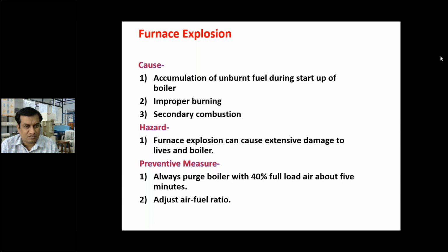So what is the hazard due to this incomplete combustion or unburned fuel? The furnace explosion can cause extensive damage to lives and the boiler. Due to unburned fuel, extra heat is produced, and that can damage lives and the boilers. So how to prevent that? Always purge the boiler with 40% of full load air for about 5 minutes.